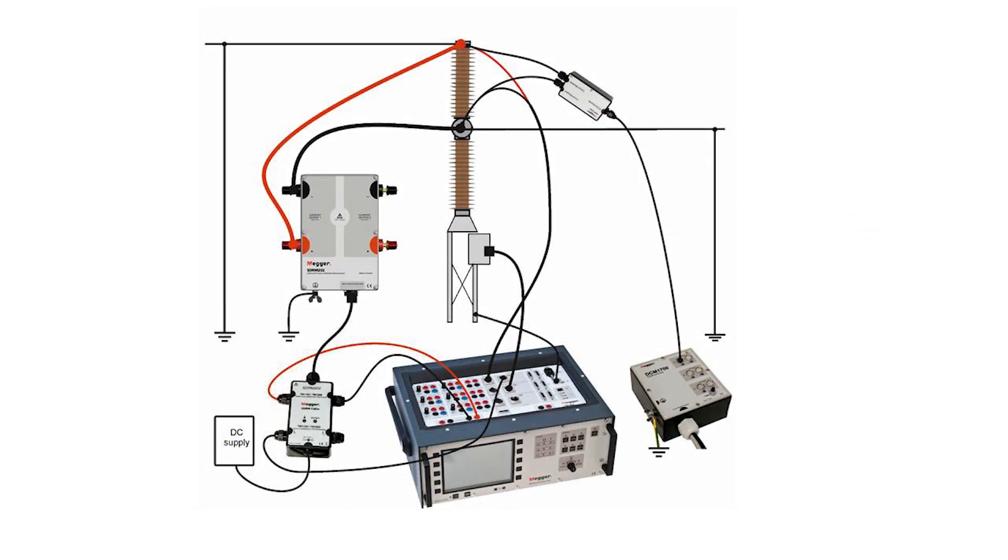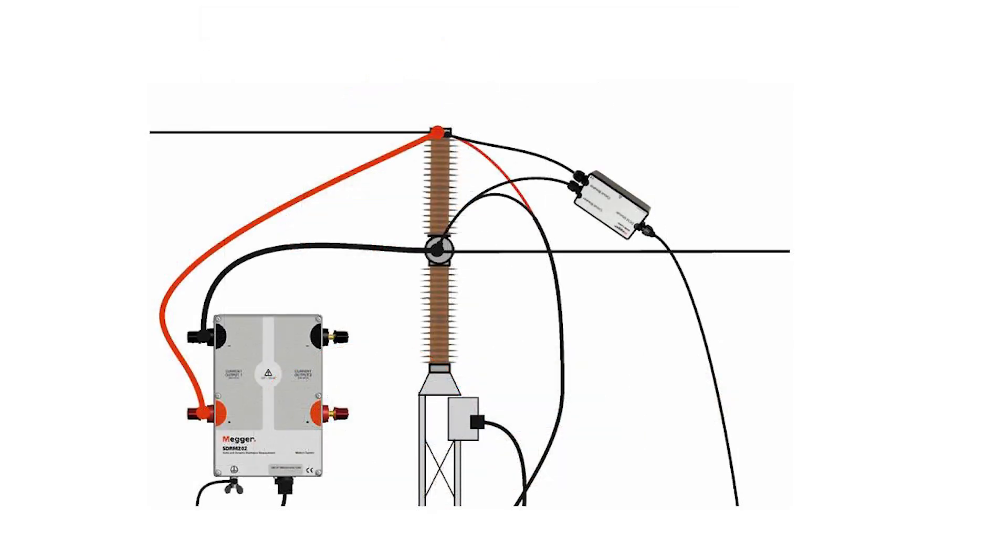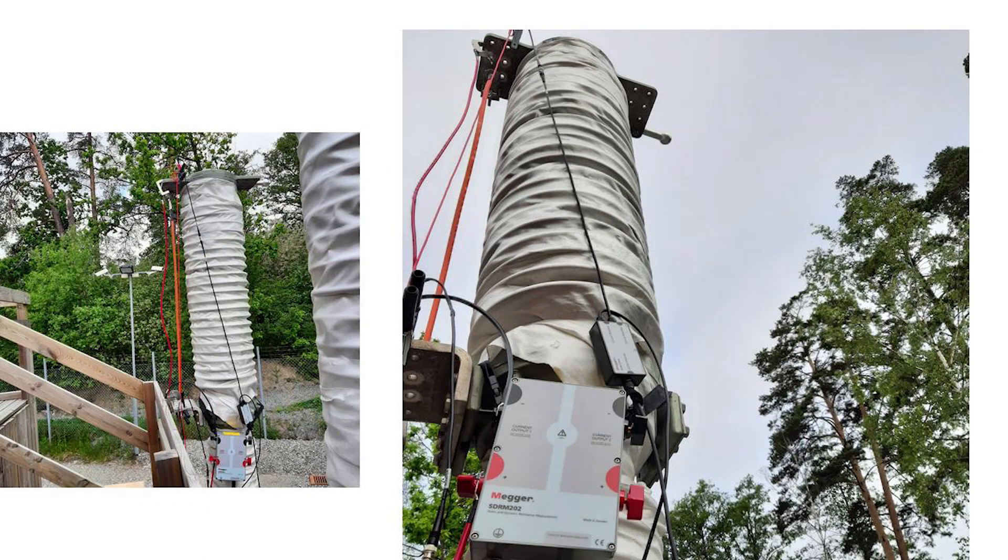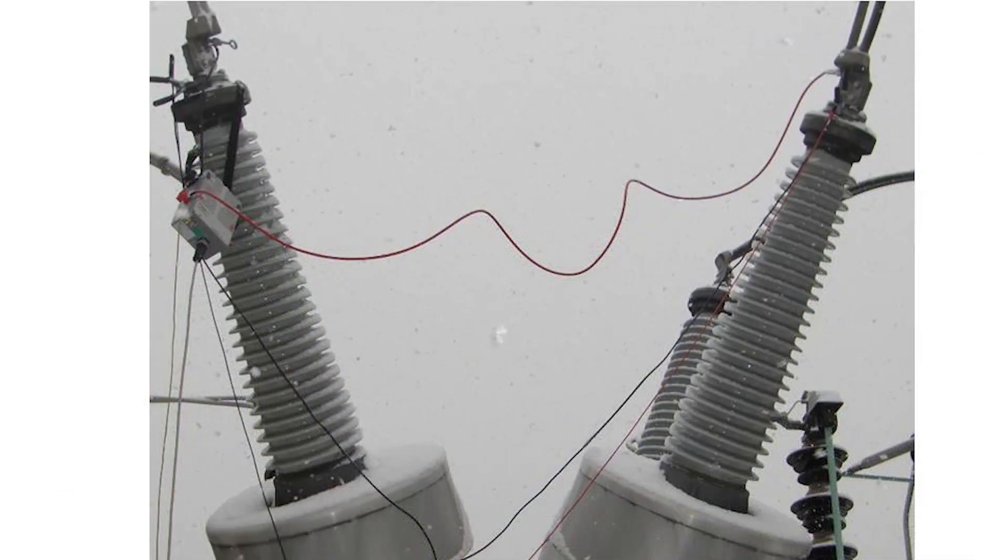Or as we show here where the SDRM-202 and the dual ground timing DCM is connected at the same time on the circuit breaker. All the connections at the circuit breaker can be done from start. You don't have the DCM timing leads connected at instrument during the DRM measurement. But they can be connected at the pole of the breaker.